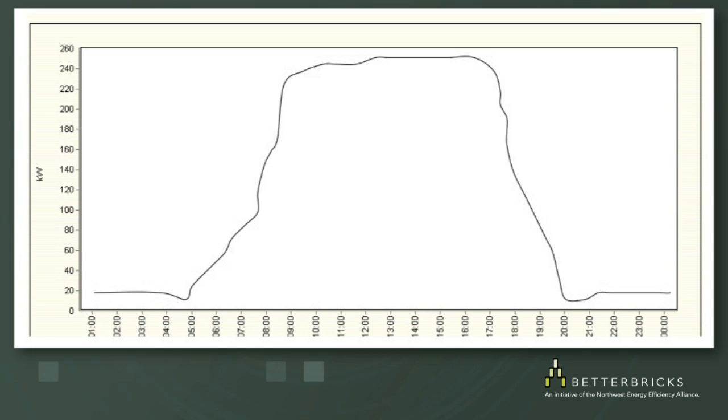So now what I want you to do is think about your own load shape. Think about what your building does and try to draw what's going on in your building. In this example here, this building, the outdoor lighting turns off between 4:30 and 5 o'clock in the morning, showing this little dip in usage. Around 5 o'clock, the building starts coming on. My guess in this facility is people start coming in, turning the lights on. And then just before 8 o'clock, the main heating and ventilation and the rest of the lighting in the building starts up. So that's when the building is mostly occupied.